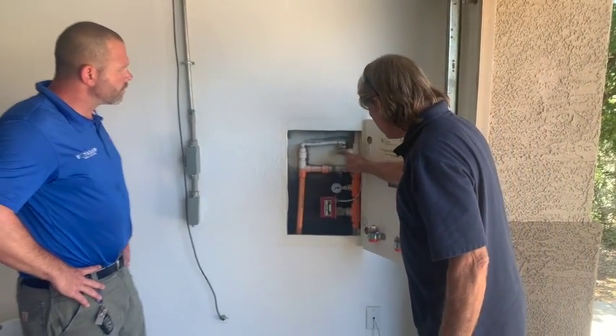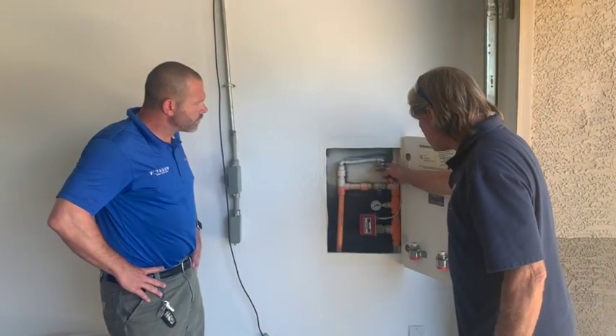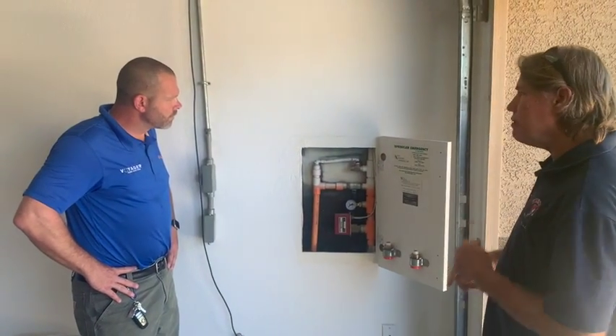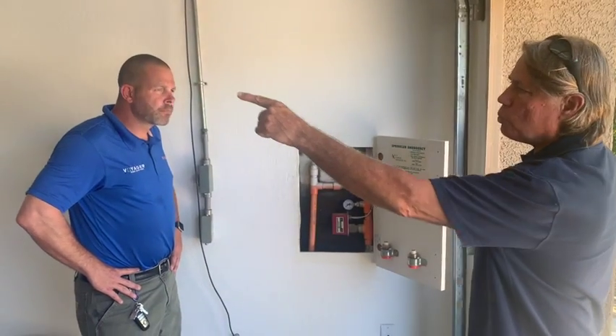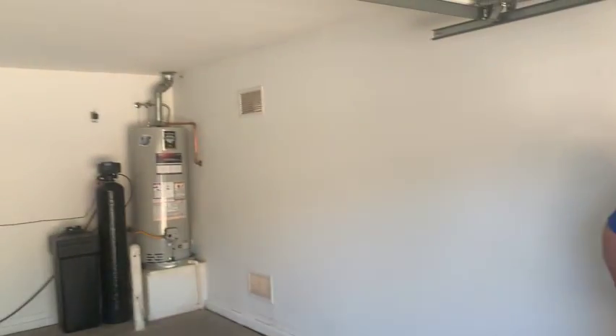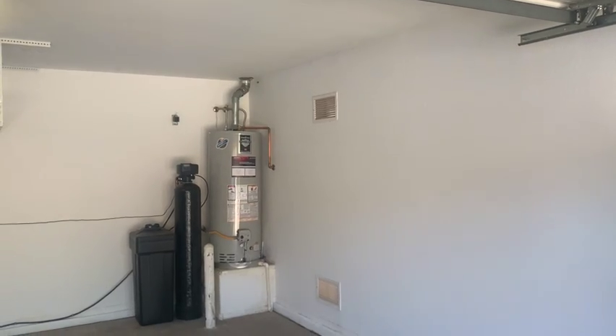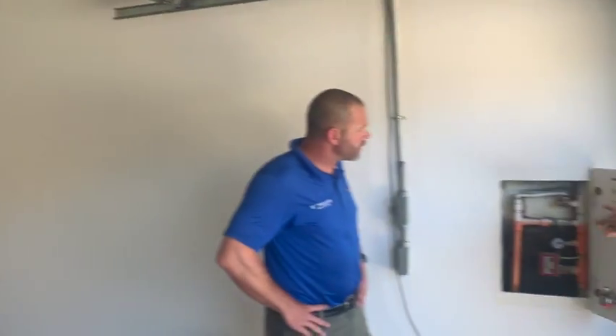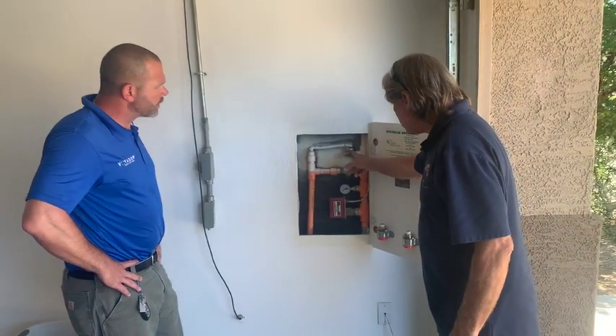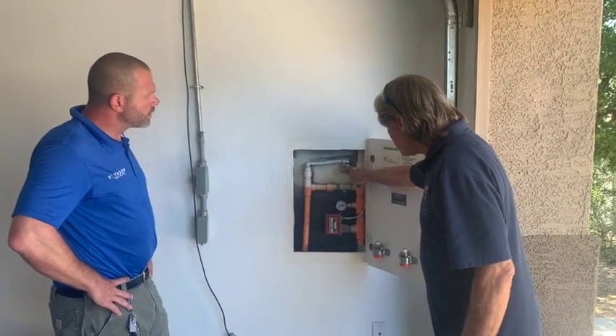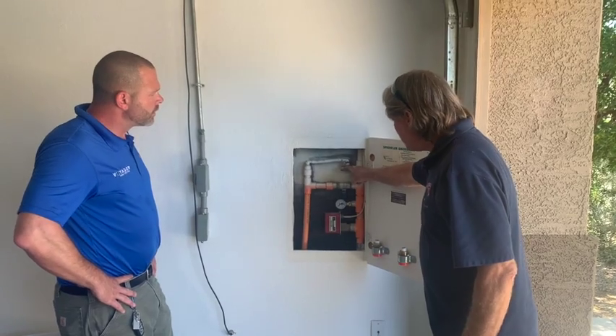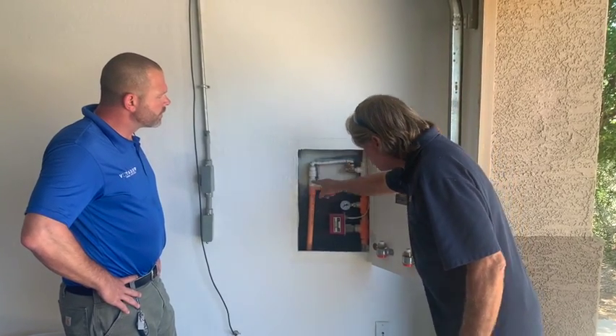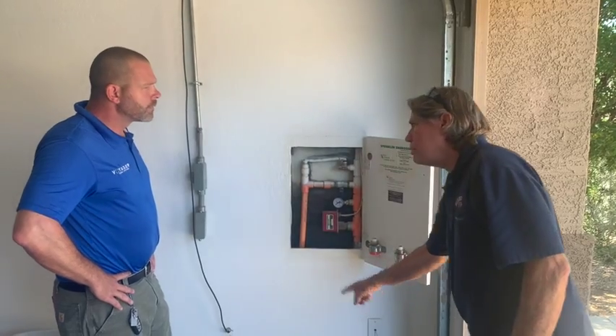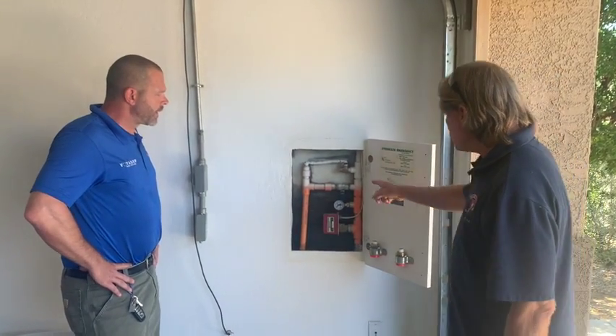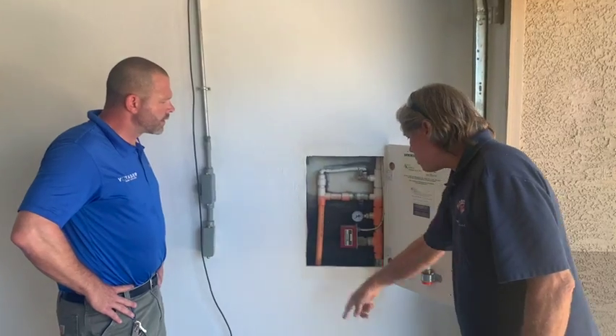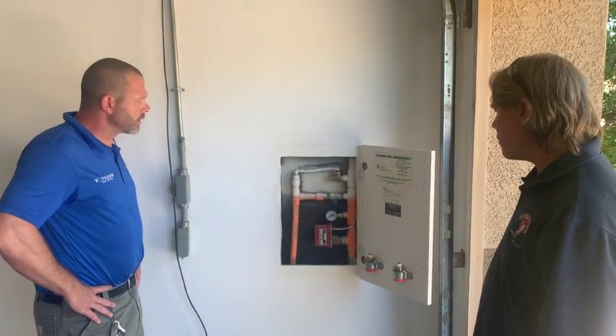The item that was leaking was this PRV, and in this case the acronym stands for Pressure Relief Valve. It's very similar to the one on the water heater over there. You see the pressure relief valve on the top? Yes. Most people are familiar with that. It's identical in that it does the same function. When the pressure gets up to, in this case, 175 psi or higher, it's going to open up and bleed off the excess pressure out that drain from the 90 you just mentioned. So this was leaking, and that was causing the calcification up there.